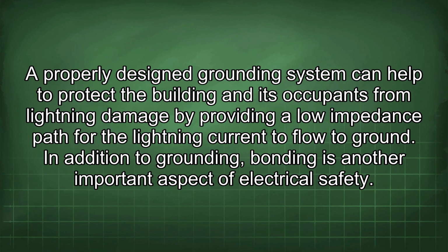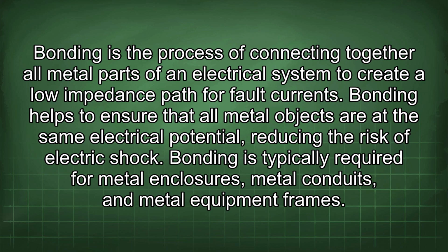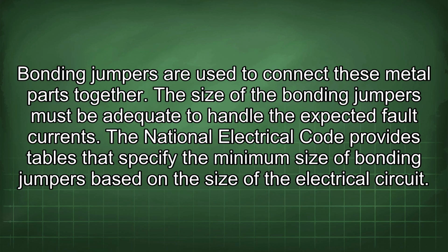In addition to grounding, bonding is another important aspect of electrical safety. Bonding is the process of connecting together all metal parts of an electrical system to create a low impedance path for fault current. Bonding helps to ensure that all metal objects are at the same electrical potential, reducing the risk of electric shock. Bonding is typically required for metal enclosures, metal conduits, and metal equipment frames. Bonding jumpers are used to connect these metal parts together.